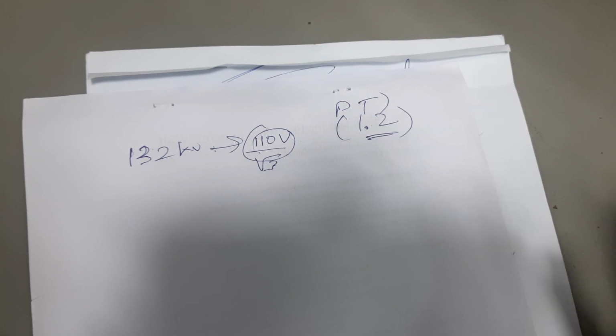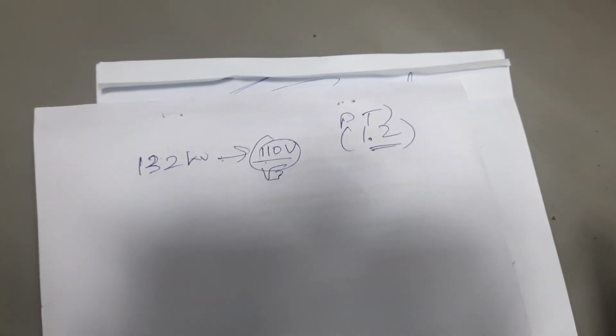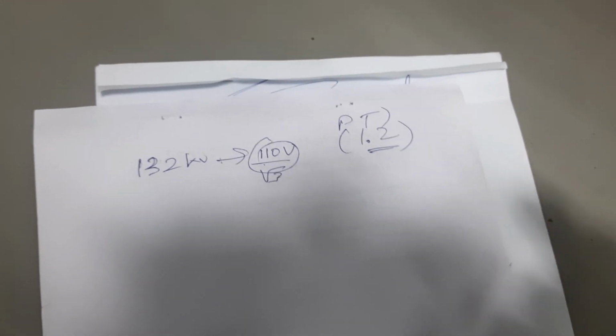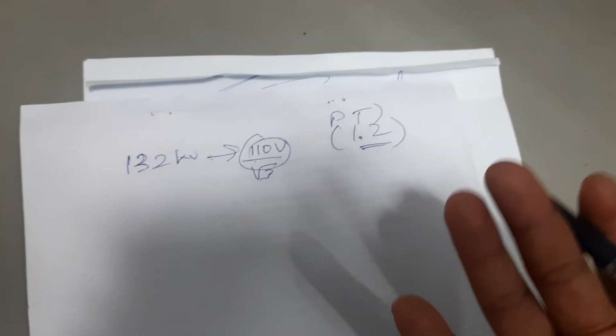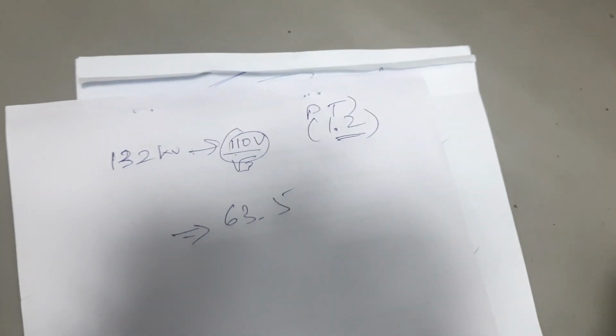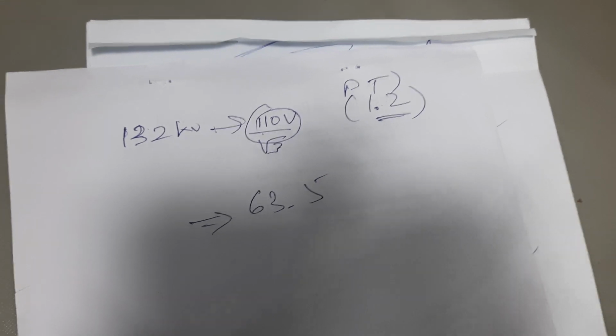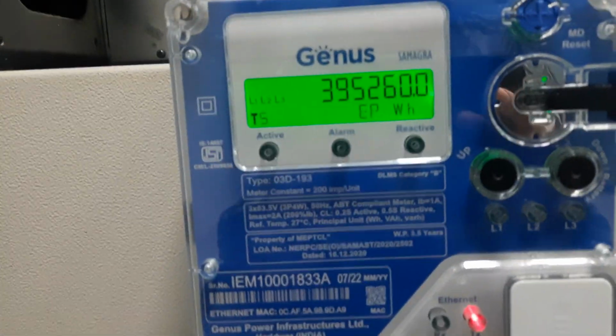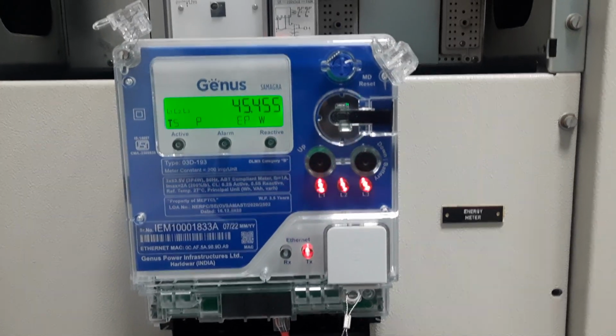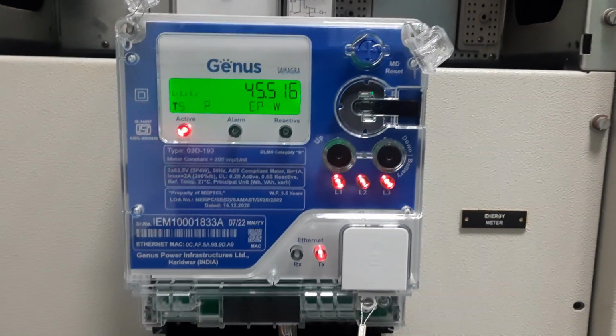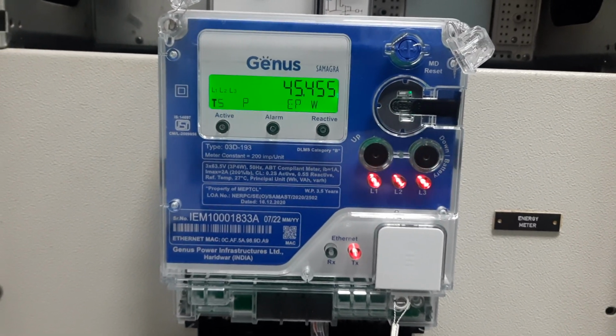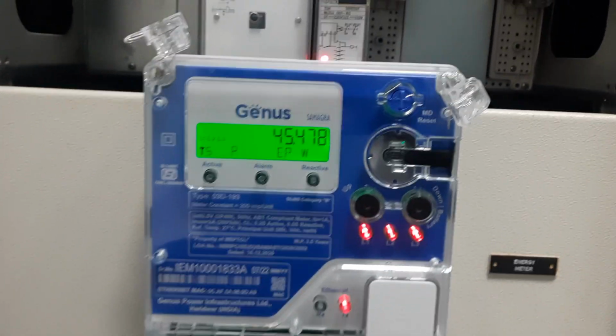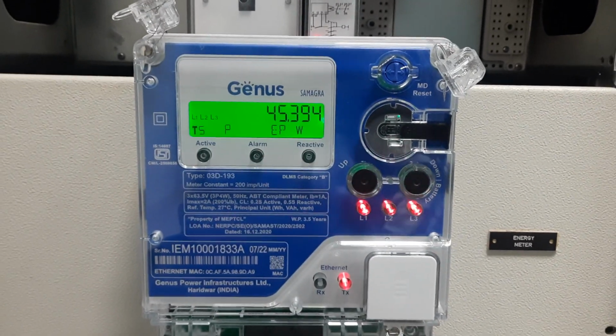Our secondary should record this because it is fixed. It cannot be like 122 or 140. The primary will be around 132, 133 or 131, minimum 131, and it can go to 134 also. So in the secondary I should be getting around 63.5, or it may be 64 or 65, depending on the primary voltage. Let me check from the meter. If I'm getting this, the connection is correct. If not, there is something wrong with either the meter or the connection. This is actually necessary for inspection also.